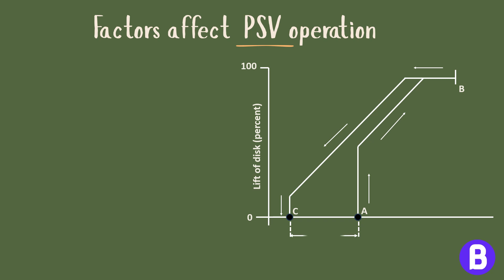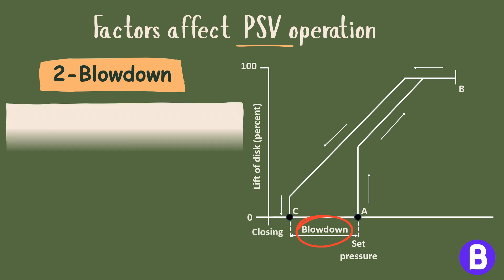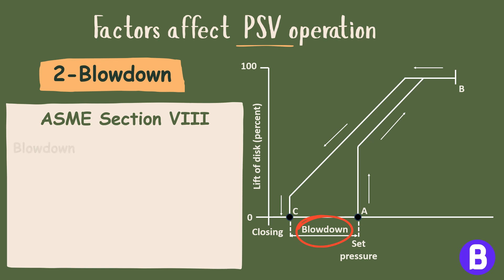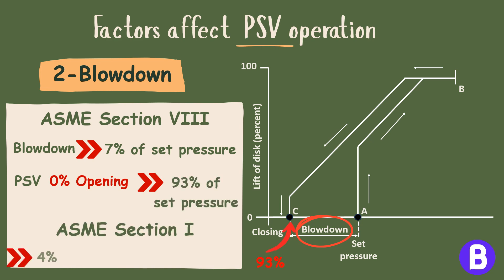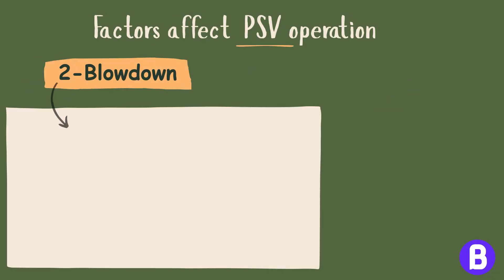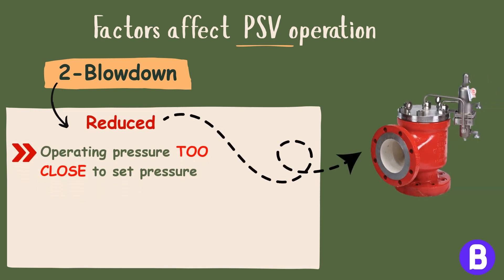Factor 2: Blowdown. Blowdown is the difference between the set pressure at which the pressure safety valve starts to open and the pressure at which the valve reseats. ASME Section 8 considers blowdown to be 7% of set pressure — in other words, the PSV totally closes at 93% of set pressure — while ASME Section 1 considers 4%, meaning the valve closes at 96% of set pressure. Blowdown should be reduced for a pilot-operated valve, as it operates at a pressure too close to set pressure, so it is considered to be 3% to avoid interference with operating pressure.